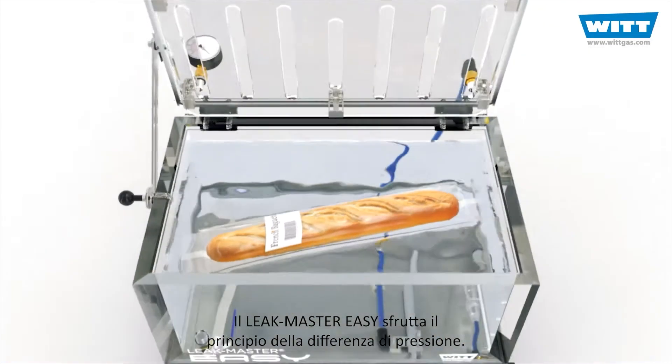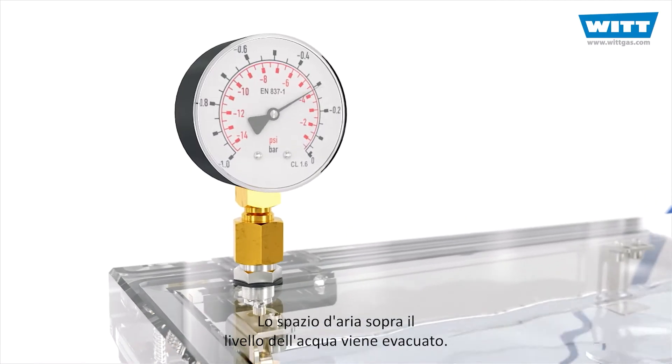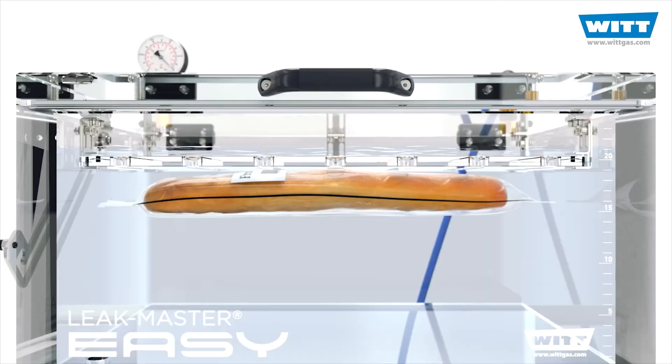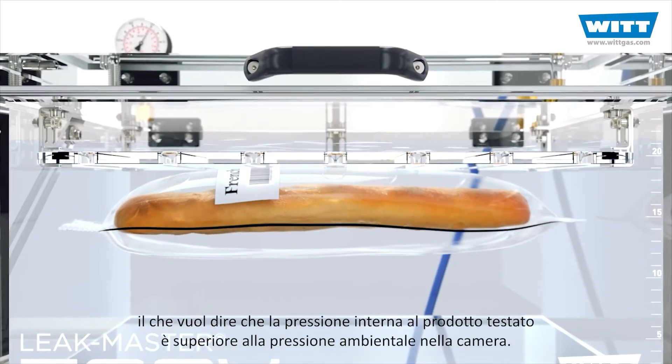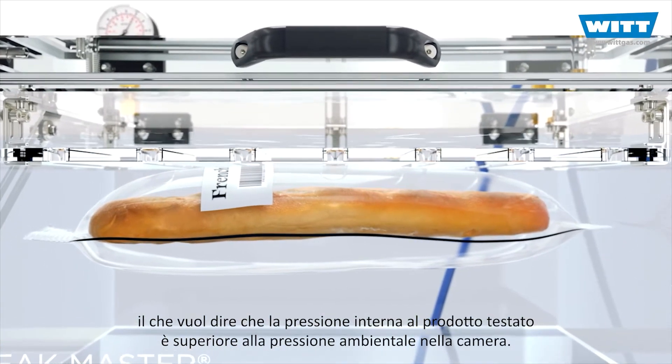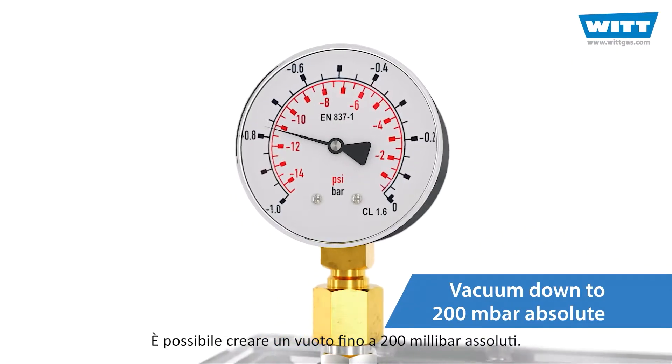The Leak-Master EASY uses the principle of pressure difference. The airspace above the water is evacuated. A vacuum is created, which means that the pressure inside the test product is higher than the ambient pressure in the chamber. You can create a vacuum down to 200 millibar absolute.